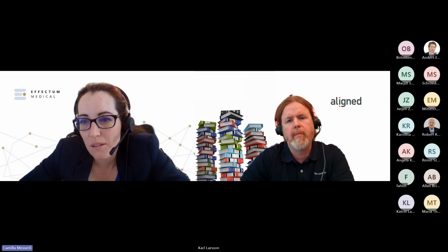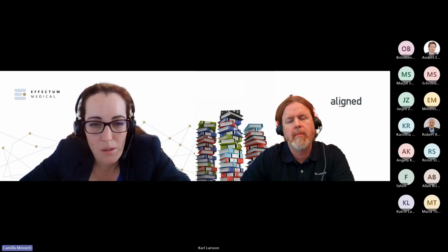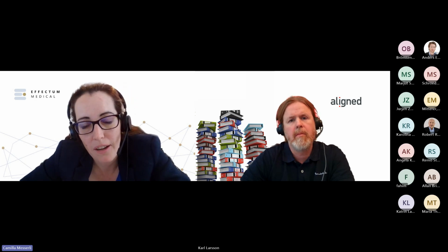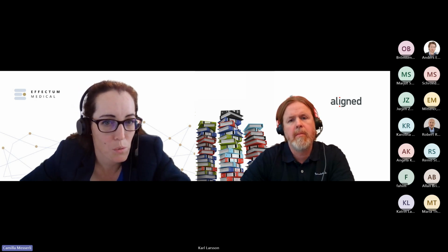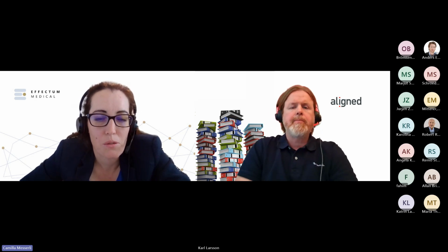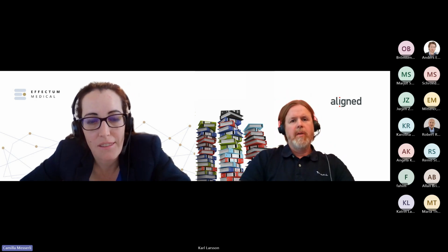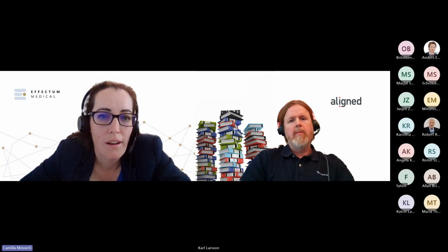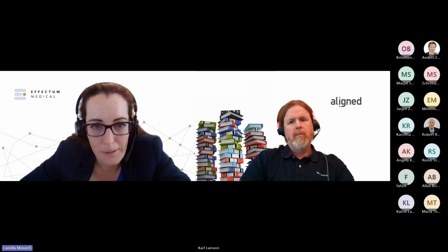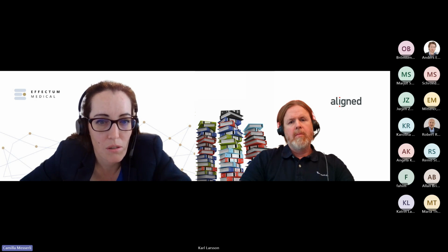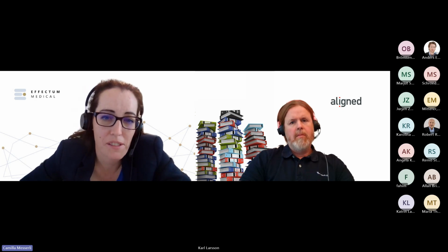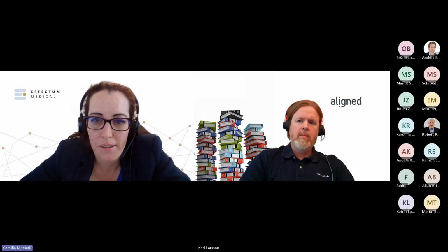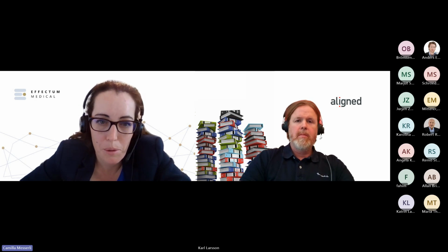But here, one of the things that you can always try to justify away is obviously the PMCF and PMPF reports. They're mandatory, but even the MDR and IVDR allow a justification why those won't be needed. So that's something that you should definitely think about. It could make sense to use a consultant, just to be sure that you're not randomly dismissing those important documents, but are actually justified to do so. That can save you a lot of time down the line, because 60% is copy-paste between the PMS report and the PMPF report. They're very similar.